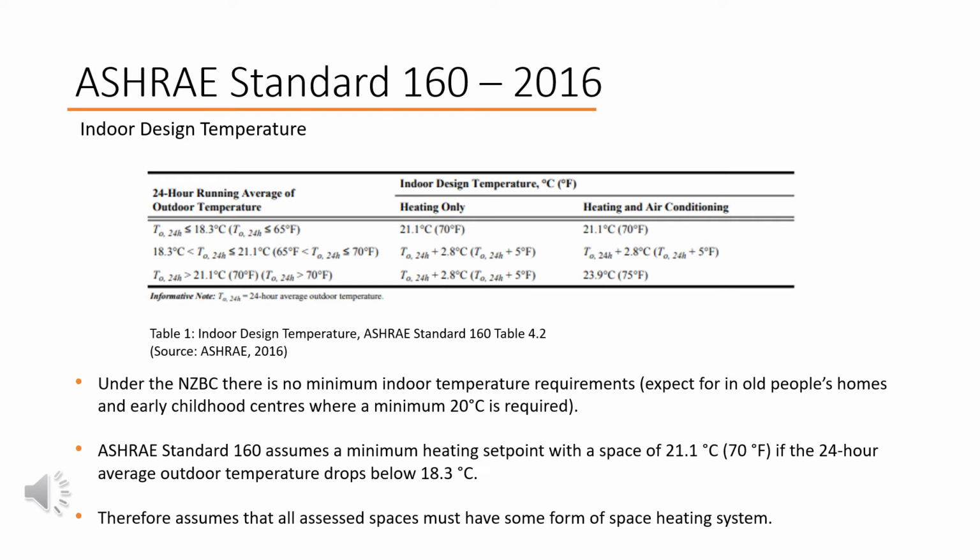So this table here shows the formula that ASHRAE Standard 160 implements to suggest the indoor design temperature. ASHRAE Standard 160 assumes that the indoor design temperature is directly related to the outdoor temperature and specifies it as one of 3 values, all dependent on the 24-hour running average of the outdoor temperature. This is particularly important for New Zealand, as the New Zealand Building Code has no minimum indoor temperature requirement, except for in old people's homes and early childhood centres where a minimum of 20 degrees is required.